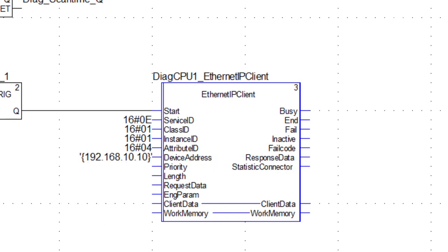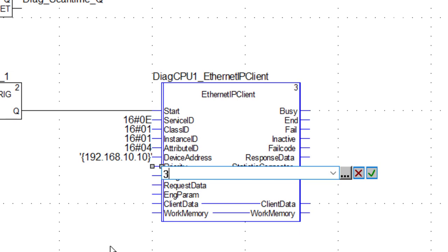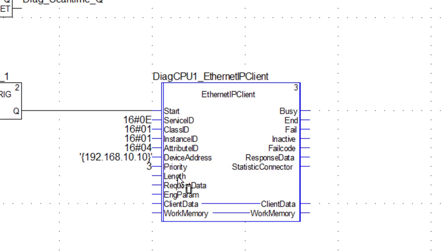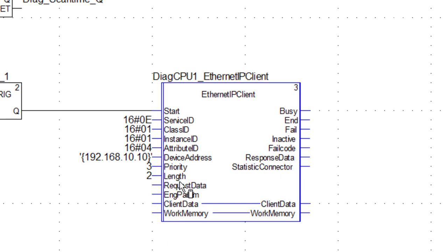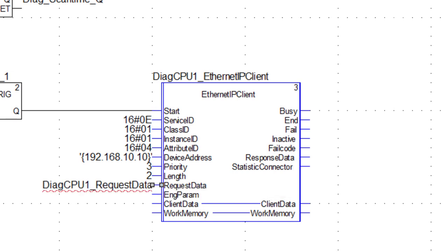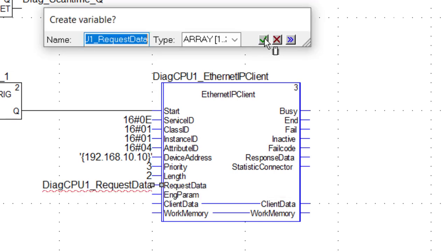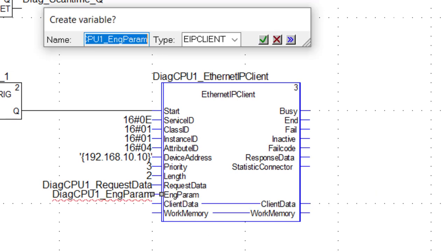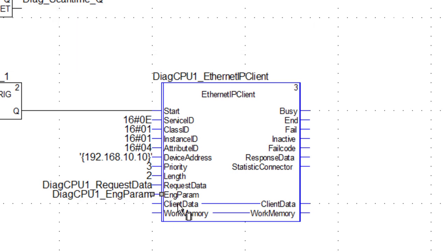For priority, typically a value of three is used for read operations, as opposed to two or one for write operations. The length parameter is used more for write-type messages and defines the number of bytes sent in the Ethernet IP query. For the remaining pins, we create variable names following a syntax of a constant prefix — in this case diagcpu1 underscore — followed by the name of the pin itself.